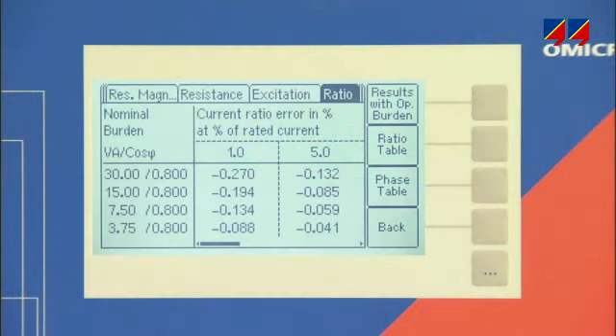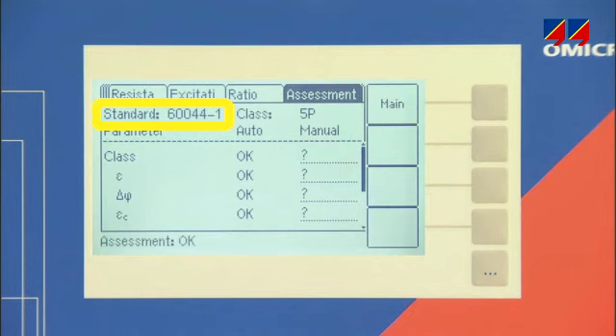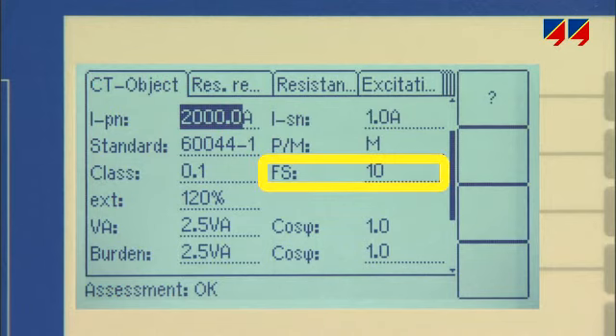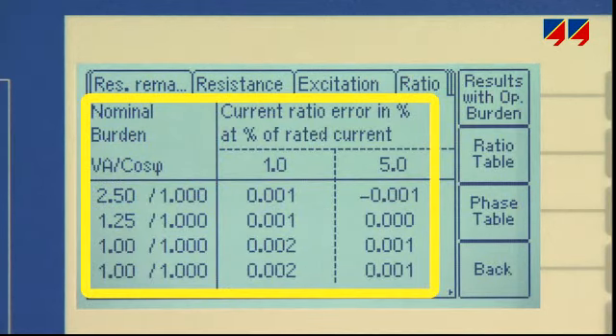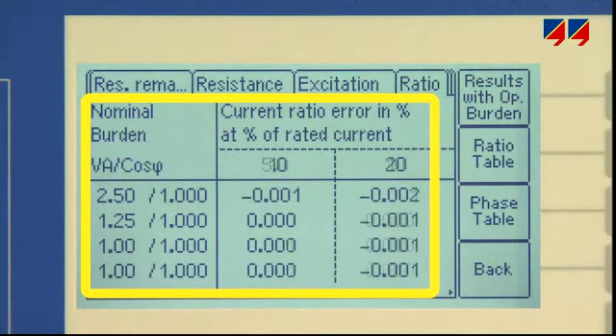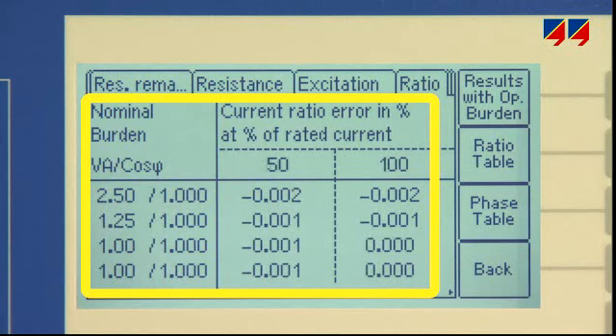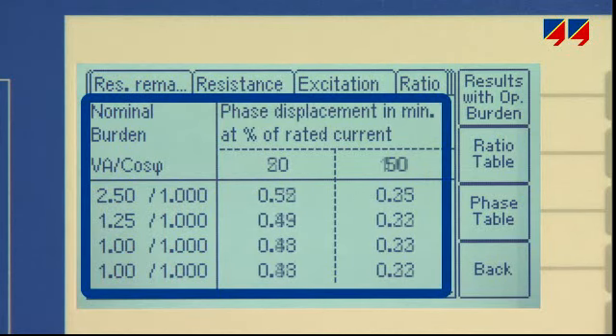For metering CTs, it measures the amplitude and phase angle accuracy for combinations of primary current and burden as defined in the relevant standard, and automatically assesses if the CT is within the specified limits. It shows the instrument security factor at the actual burden, verifying the meter's protection against overcurrent. Amplitude and phase error can also be calculated for any combination of primary current and burden required by the user.